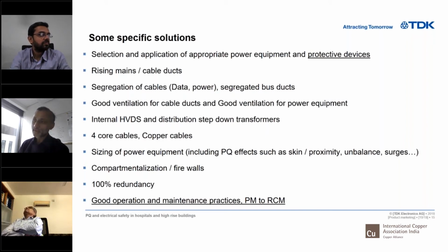Then I definitely would recommend the use of copper cables and 4-core cables. Copper cable, not because the seminar is funded by copper promotion, but because they have much lower losses. They have much better skin and proximity performance when it comes to harmonics. And in my opinion, in some cases, I've even used 5-core cable, where the neutral is double, because the neutral carries more current than the phase. And one can prove with certain kinds of loads, harmonic loads, the neutral current can be much more in terms of magnitude. And also the neutral currents will be at 150 hertz, the third harmonic, which means you need to provide for the proximity and skin effect.